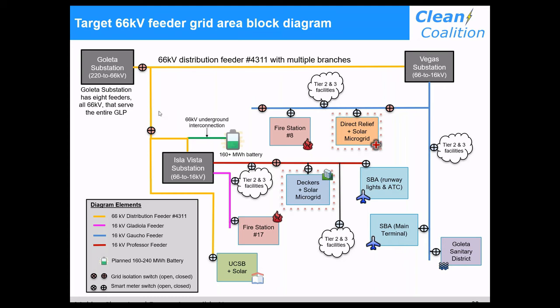Now let's say that somebody runs into a power pole right here, separating this section from that first grid isolation switch that opened and this next one. Then we would open here and we would open this grid isolation switch, and this can be automated. This isn't like somebody has to be there flipping switches. This can be automated based on logic. And if this grid isolation switch opens, then the battery is still interconnected and can serve and provide the grid forming function for this whole section of the feeder, which can keep UCSB online and make sure all that solar at UCSB can come up and keep this portion of the grid working in concert with that massive battery.